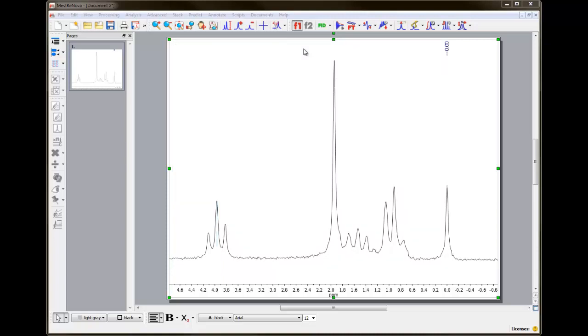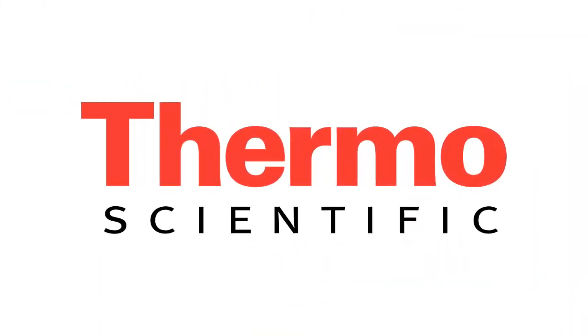The order in which we apply most of these processing tasks is not critical. In practice, however, it's better to zero fill and baseline correct your data before phase correction. In this video, we explored basic processing techniques of PicoSpin JCAMP data using the Mnova NMR software. We described various processing tasks, such as zero filling and apodization, and provided guidance on how to set their values. For a more detailed description of data processing, please refer to Mnova's user manual.